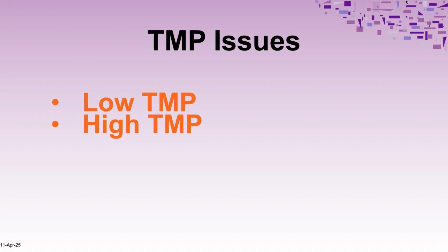And a saturated venous transducer protector actually can cause that kind of TMP because the machine can no longer electronically monitor the pressure variations in that dialyzer. So if you have a wet transducer, make sure that you do dry it. It's almost like if the transducer becomes wet, it's almost like clamping it. And that's the effect that you have. So if you have a venous dislodgement and you have a wet transducer, is that venous reading going to change? It won't.